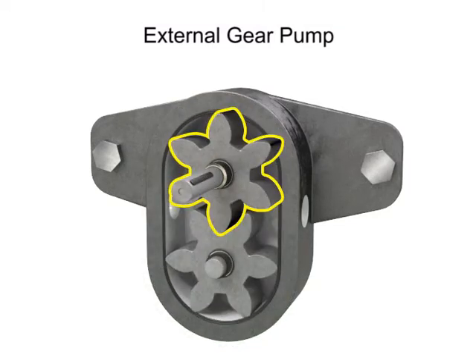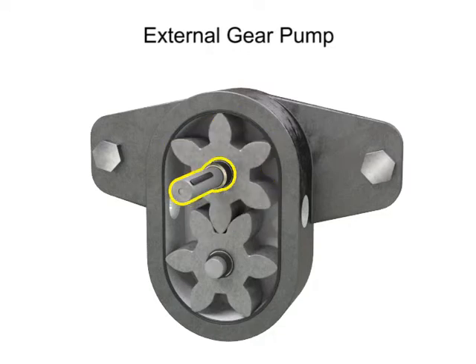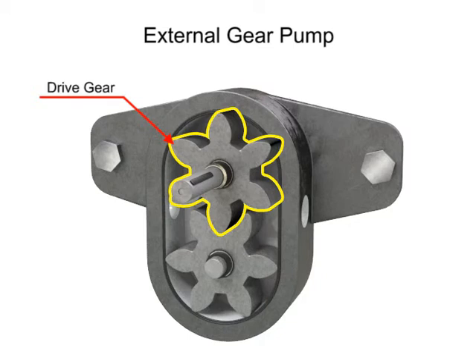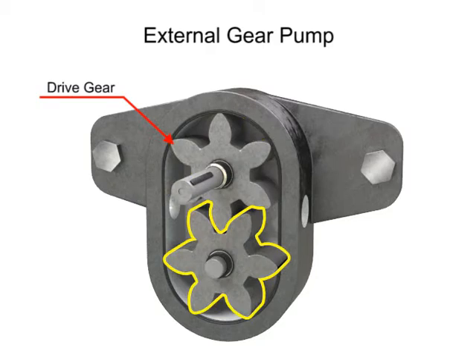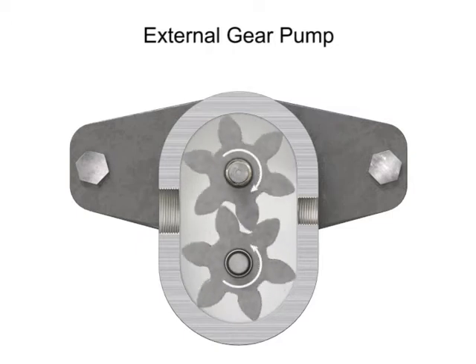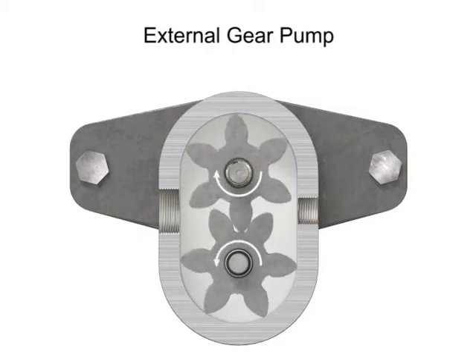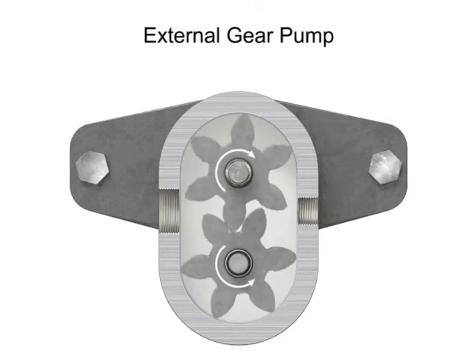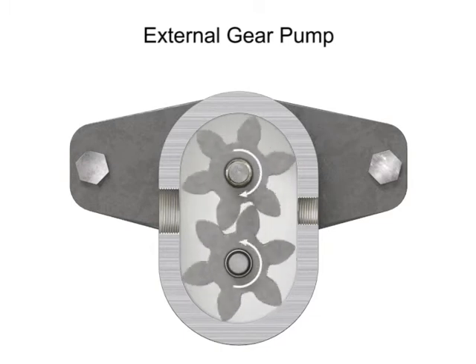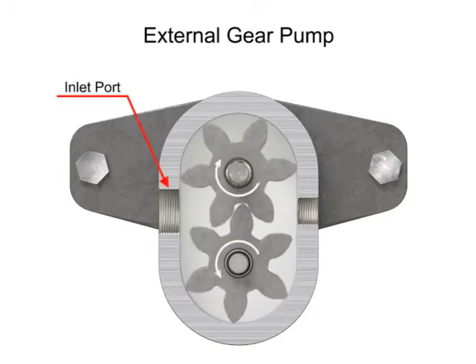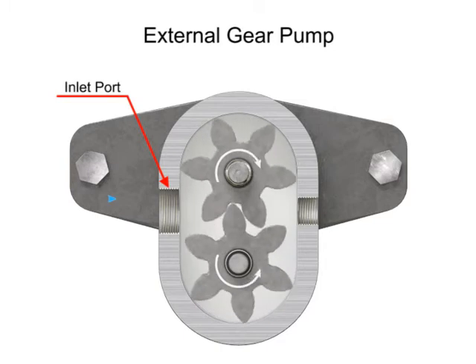One gear is driven by a motor connected to a shaft. This is called the drive gear because it is driven by a motor, and it in turn meshes with and drives the movement of the second gear. As the gears rotate away from each other and come out of mesh, they create an expanding volume on the inlet side of the pump, creating a vacuum at the inlet port allowing fluid to flow into the pump.